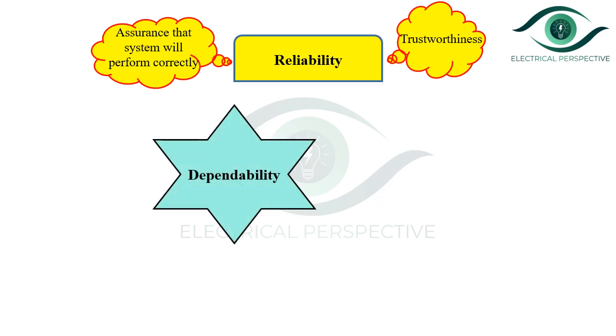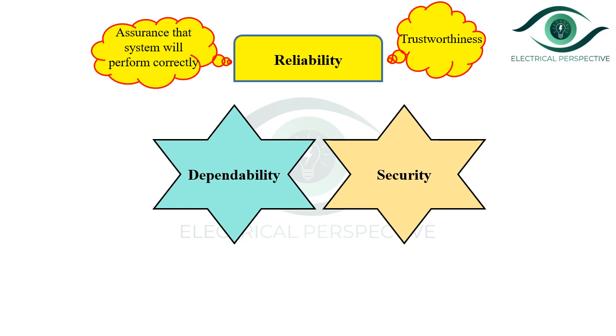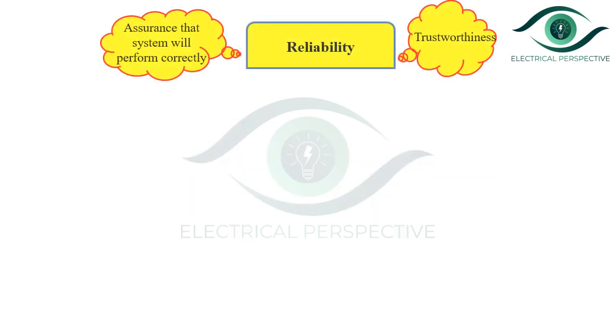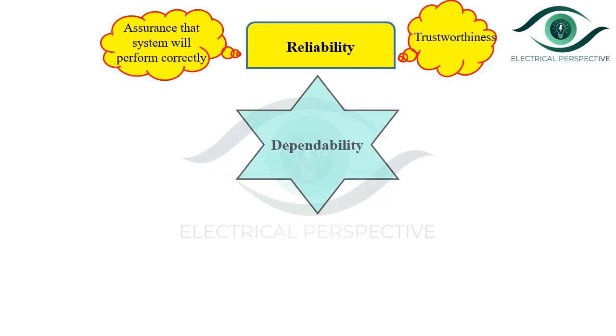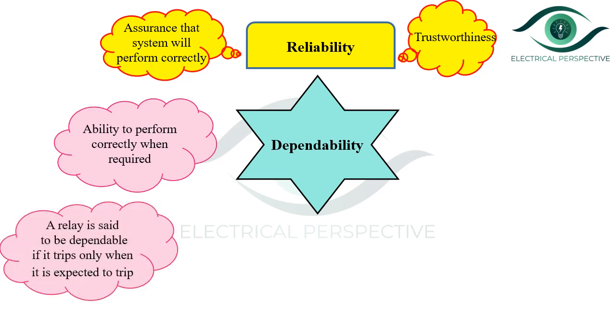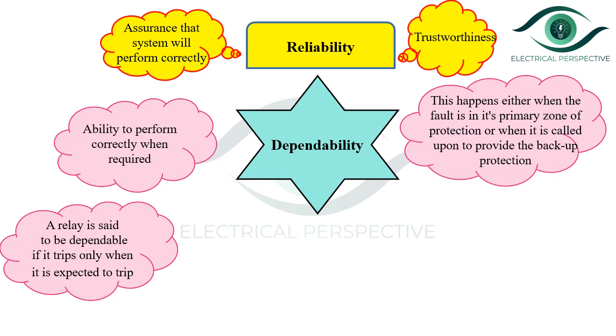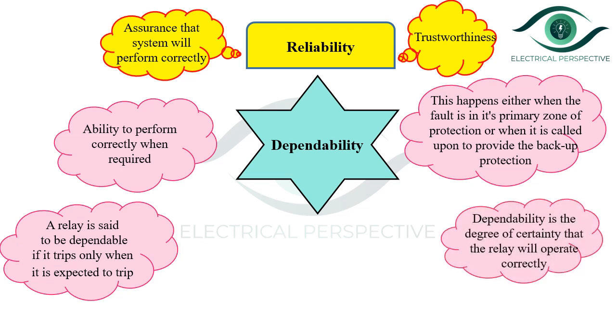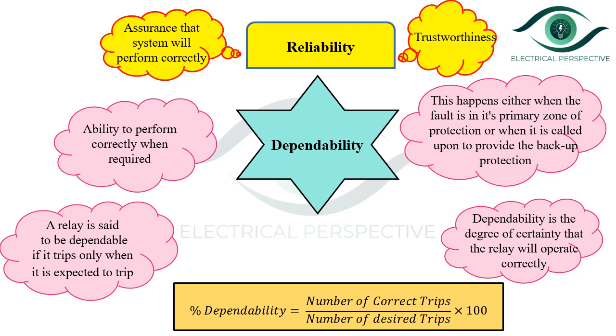There are two aspects of reliability. The first is dependability: the ability to perform correctly when required. A relay is said to be dependable if it trips only when expected to — either when a fault is in its primary zone of protection or when called upon for backup protection. Dependability is the degree of certainty that the relay will operate correctly. Percentage dependability = (number of correct trips ÷ number of desired trips) × 100. Dependability can be improved by increasing the sensitivity of the relaying system.